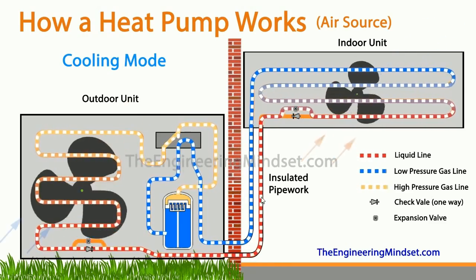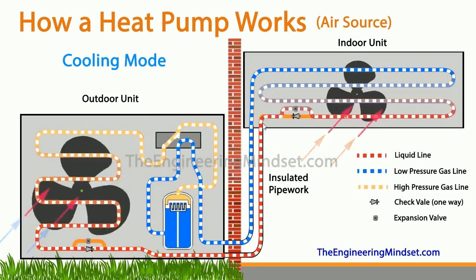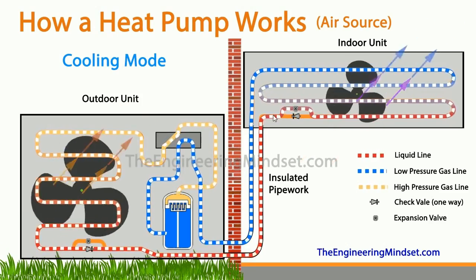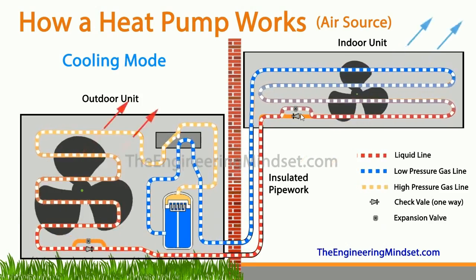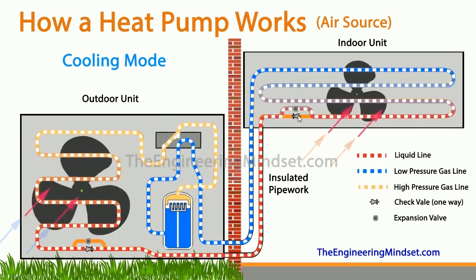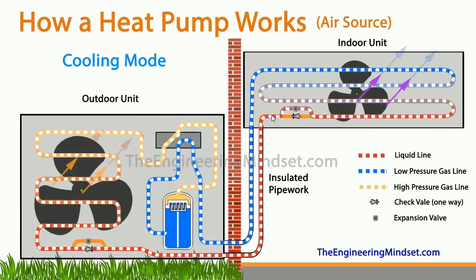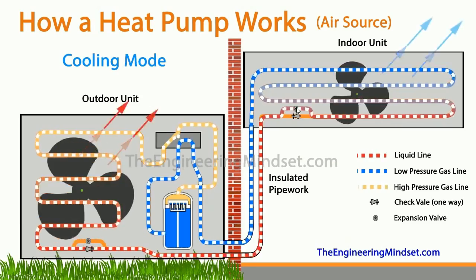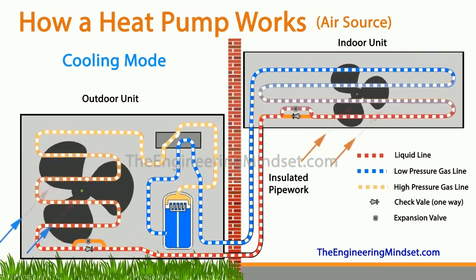Now, as that liquid refrigerant is being forced this way up into the indoor unit, it comes along and hits the check valve, and you can see it can only flow in the opposite direction, so that will not be allowed to pass through there. Instead, it will head over and pass through the expansion valve instead.